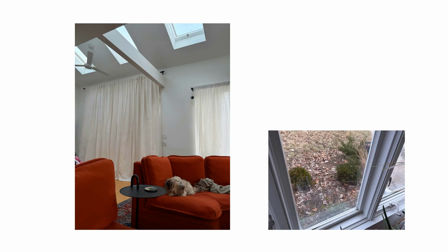So if you are designing a building with a space on the inside of the exterior wall that has, let's say, a high relative humidity for whatever reason, a gym locker room that has showers and saunas and steam rooms, or obviously a pool or something like that, you have to take care to really insulate the heck out of your exterior wall then, because you have a much higher chance of getting condensation on that wall because there's so much humidity in your air, right? Just by a function of what the space is being used for.